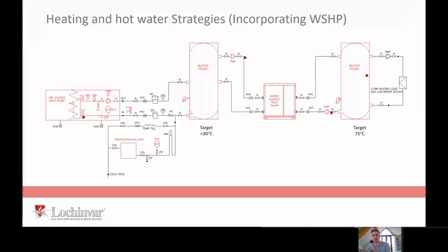But that's assuming the building can accept a lower flow temperature. If the building can't accept that lower flow temperature and you need to flow at these inflated values to be able to utilize your existing emitters, if it's a retrofit, this is definitely a very easy, from an application point of view, way to go. If down the line you decided that you were going to upgrade your emitters so you didn't need the increased flow temperatures, absolutely fine, because all you'd do is turn down the temperature of this thermal store here.